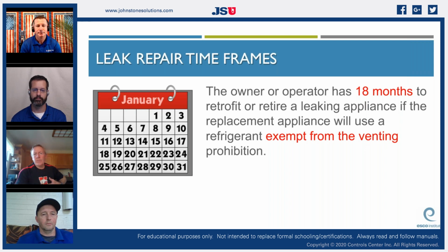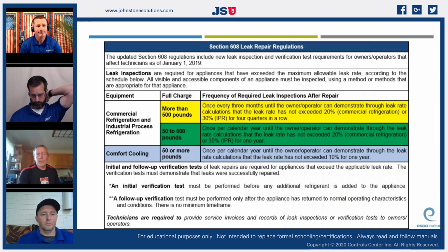Yes. The owner or operator has 18 months to retrofit or retire a leaking appliance if the replacement appliance will use a refrigerant exempt from the venting prohibition. So they give you an extra 6 months if you're going to go to a non-ozone depleting refrigerant. Correct. This eye chart, a lot of people lose their minds on because they're trying to memorize everything on here.